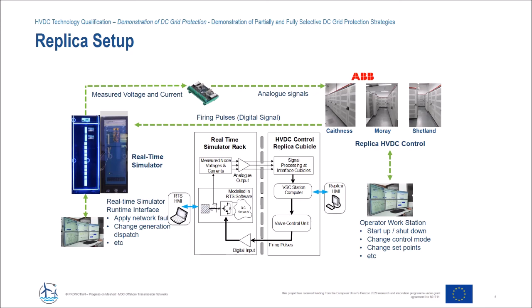In this instance, we used the replica model as a basis. It's a much more complicated model, as there's much more input and output. It wasn't immediately suitable for this testing, as it was never designed for DC protection testing, since there's not currently a DC breaker in the scheme as it's designed. So we had to start with that original replica model and move the element where we're introducing the DC breaker and the line into the small time step frequency dependent model so that we could assess the IED performance. It let us check another type of interoperability.